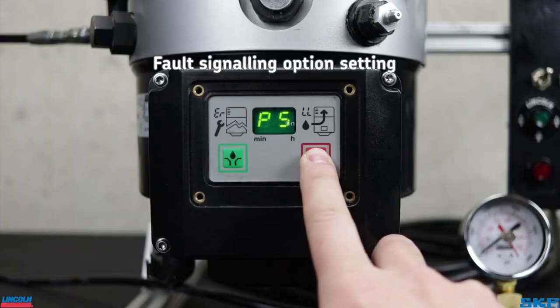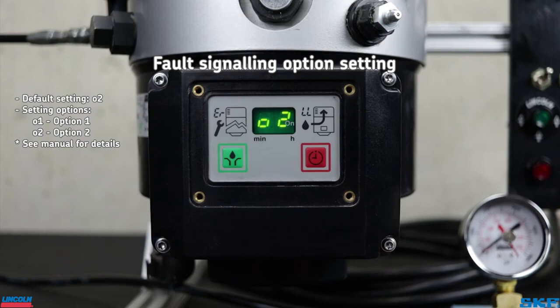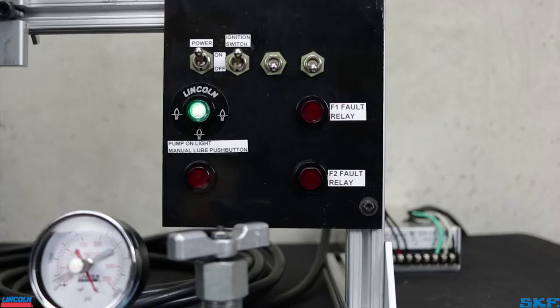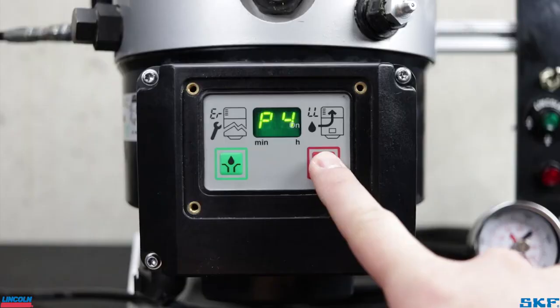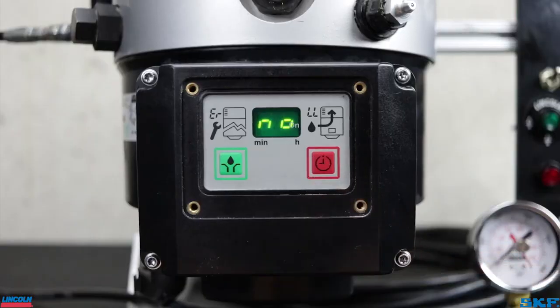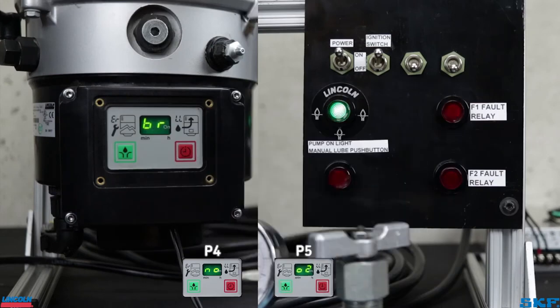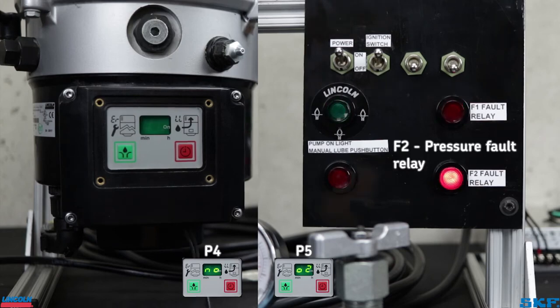P5 is the fault signaling condition. Factory setting is O2 or option 2 as shown here. This means the different fault signals are separated between the 2 fault relays. An example, with P4 set to normally open and P5 set to O2, if you receive a low level code on the unit, it will close the F1 relay contact on the board and illuminate the corresponding light. Should a pressure error fault occur, the F2 relay contact will close and illuminate the corresponding light to signal a pressure fault.